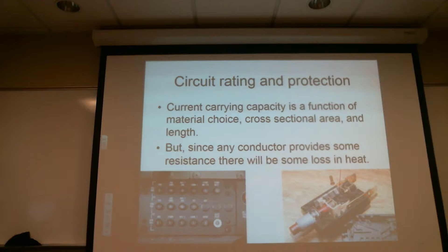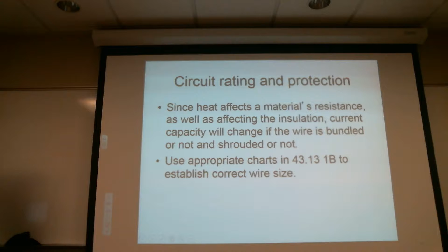Anytime we're talking about heat, we really have two equations we have to deal with. The first is how much heat will it generate. The second is how much heat can it reject over time. Right? If it can reject all the heat it can collect, then it'll never get hot. However, if we insulate it with a bunch of other wires, then it's not going to be able to reject heat nearly as quickly. So it'll tend to run warmer. So that's why those different charts for in a bundle, in conduit, single free air, and then of course limited duty versus continuous duty.